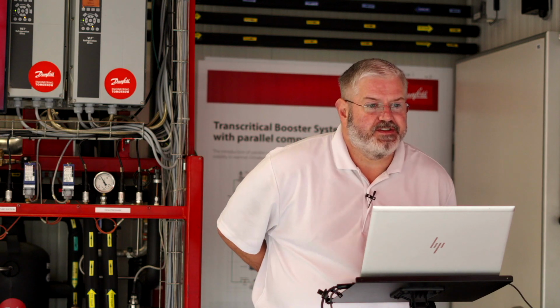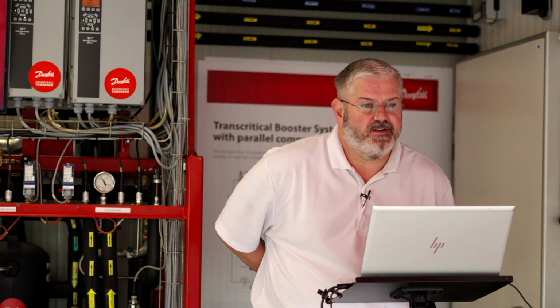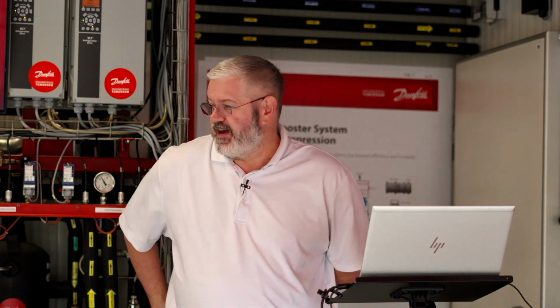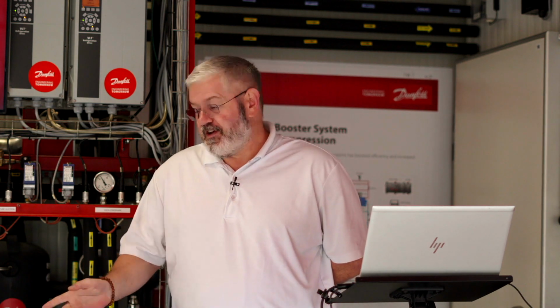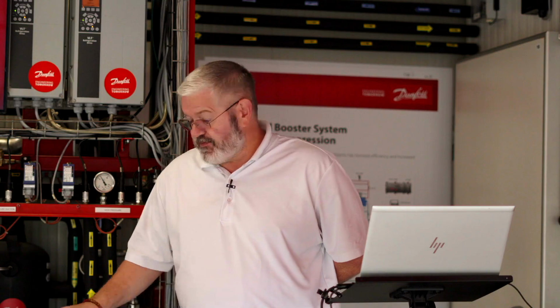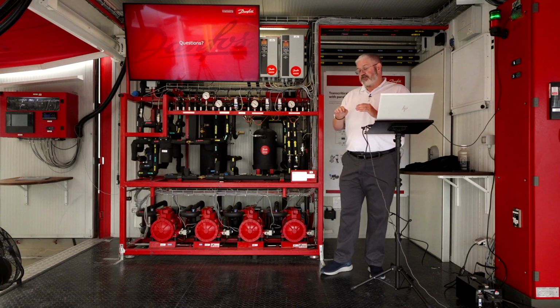Parallel compression just there when you need more compressor to handle the load. Is there another reason? Great question. Question is, is parallel compression there for when you need more compressor load, or is there another reason? That's what we're going to jump into here in about 10 or 15 minutes. Short answer is it serves a different purpose. It's going to deal with the flash gas that builds up in the top of the flash tank. They're going to handle that load at a higher temperature so that we can have energy savings dealing with that refrigerant that's kind of already spent at that point.